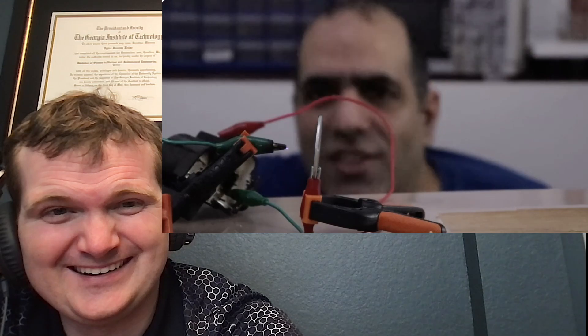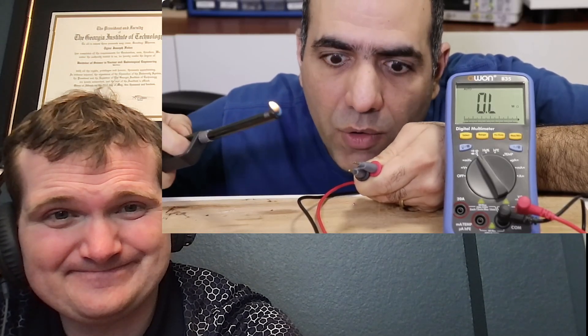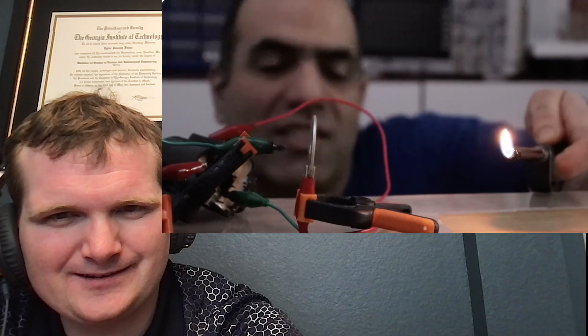When he puts a flame between the terminals it immediately arcs — flaming hot air is ionized and has very low resistance for high voltage. The closer the terminals are, the higher the current; high current heats the air, which ionizes better and the arc sustains itself. Incident energy is proportional to current, which is why at a nuclear plant some of the highest arc flash risks are on the low side of a large transformer — interesting point.